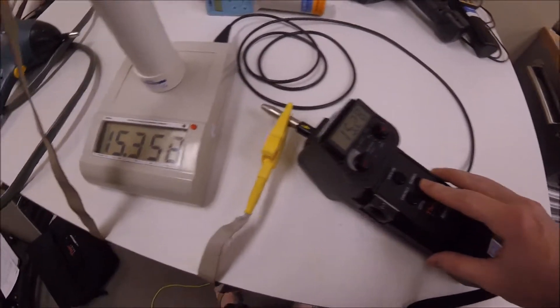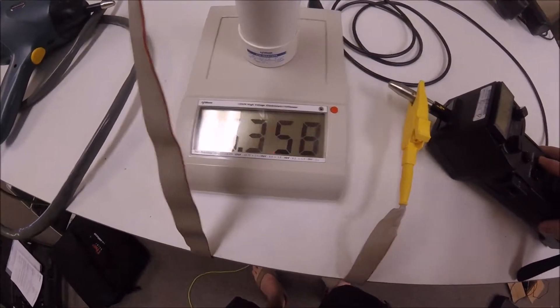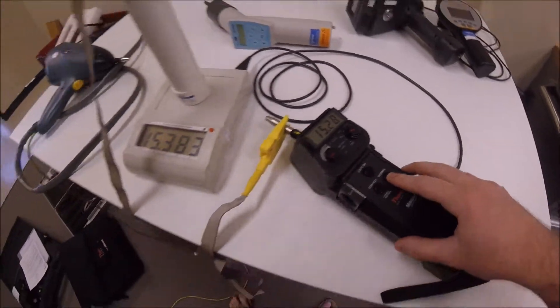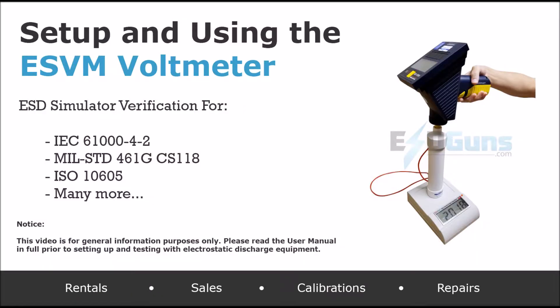Keep in mind this can't be substituted with the current verification technique also required to ensure proper functionality of an ESD gun.